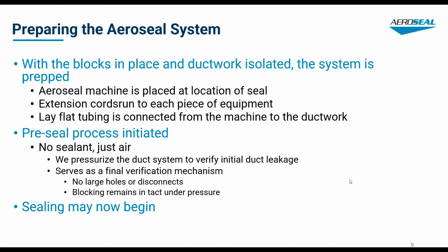The pre-seal process is initiated. We're just pressurizing the duct system, not using any sealant during this step. We pressurize it to verify the initial duct leakage. This serves as a final verification mechanism, checking for no large holes or disconnects, and confirming the blocking remains intact under pressure.